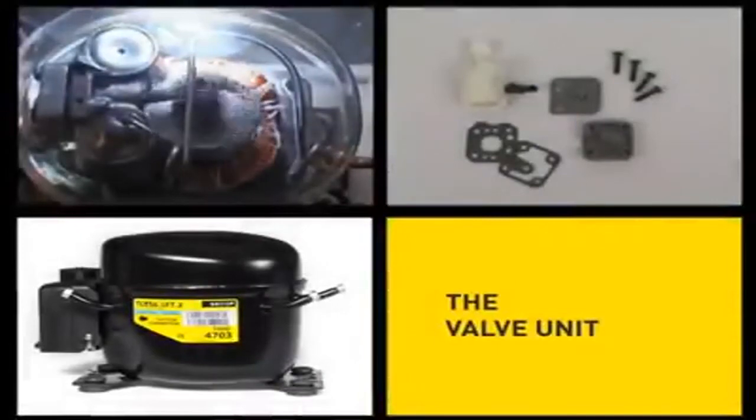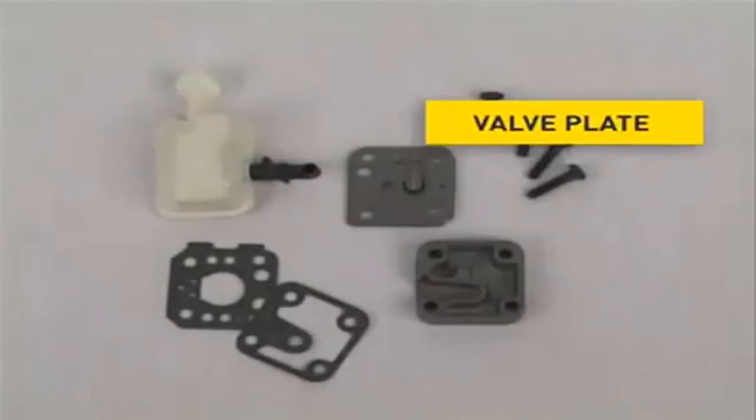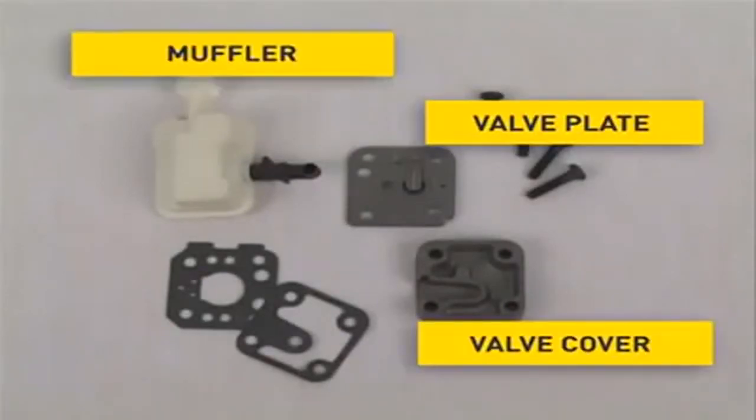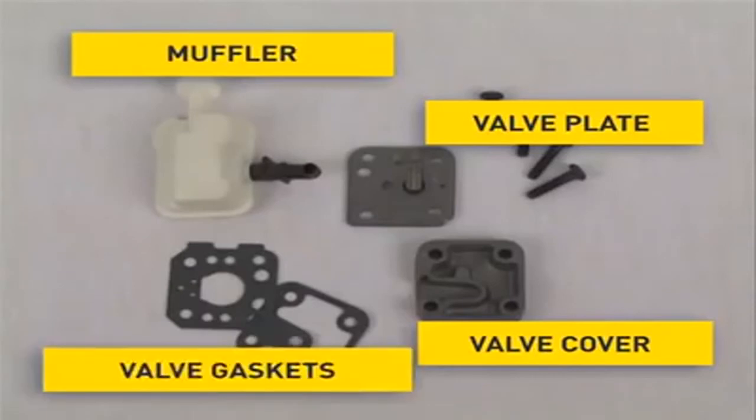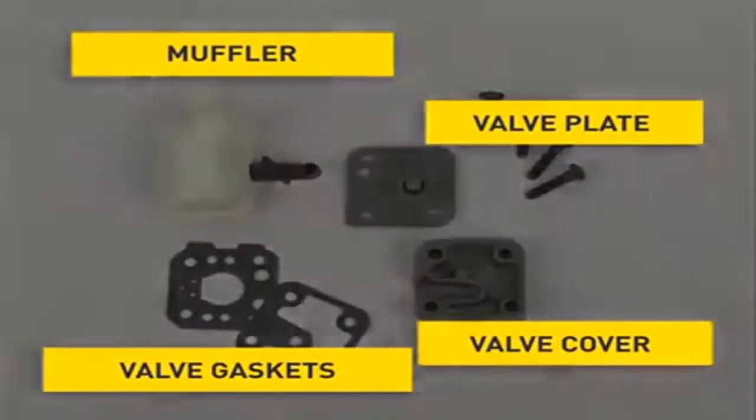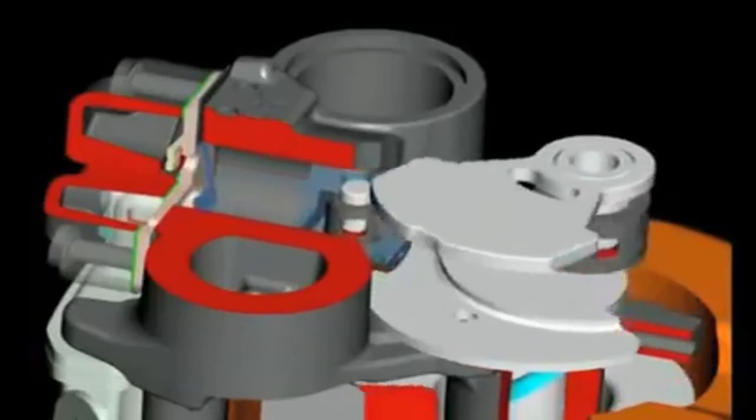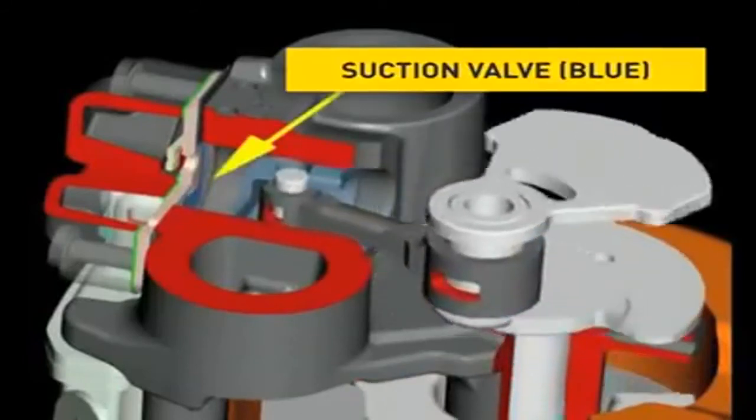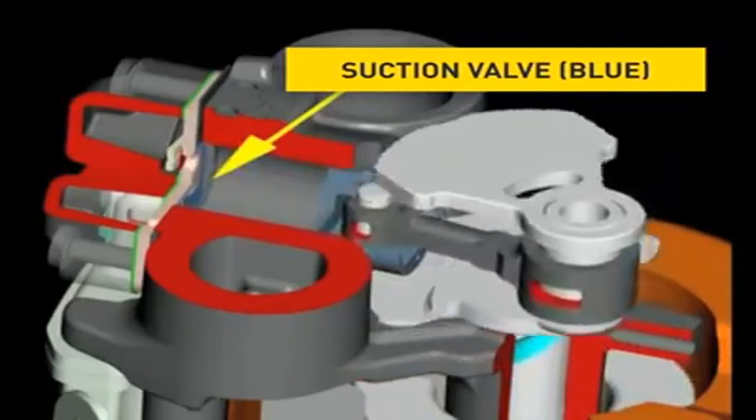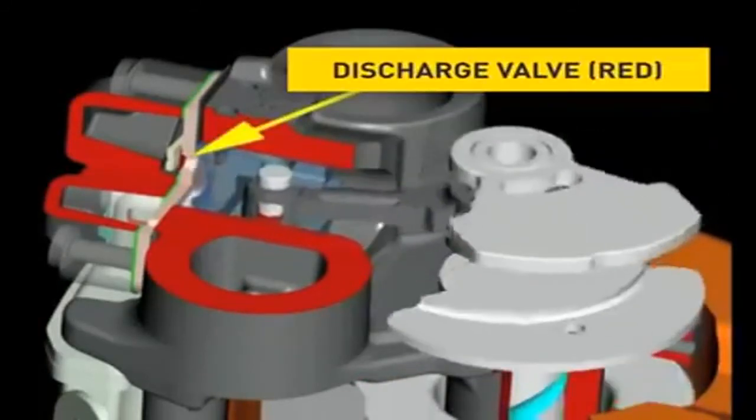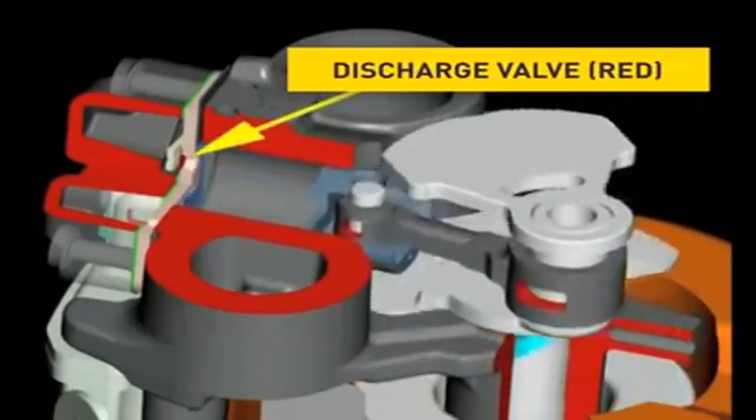The valve unit essentially consists of a valve plate, a valve cover, a muffler, as well as two valve gaskets. The suction and the discharge valve are installed on the valve plate. Both valves are reed valves made out of spring steel and they open and close the openings of the valve plate during the suction and discharge process respectively.